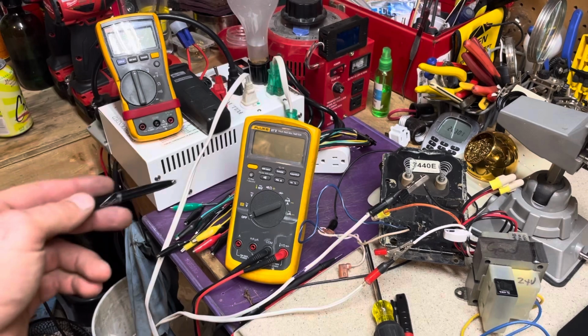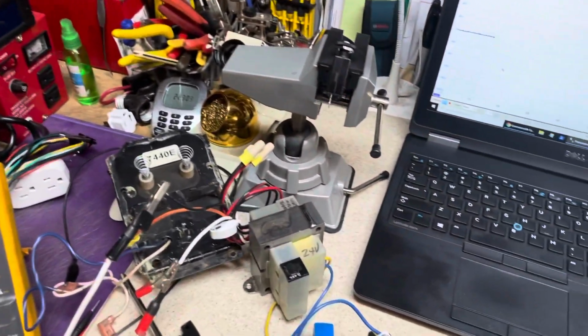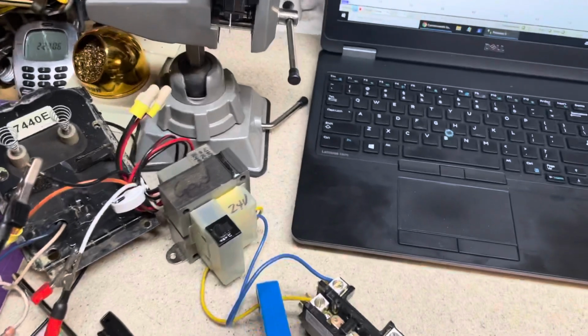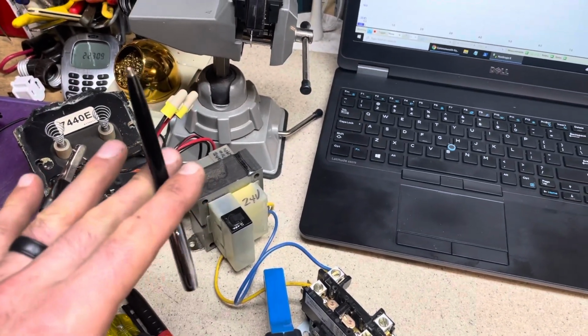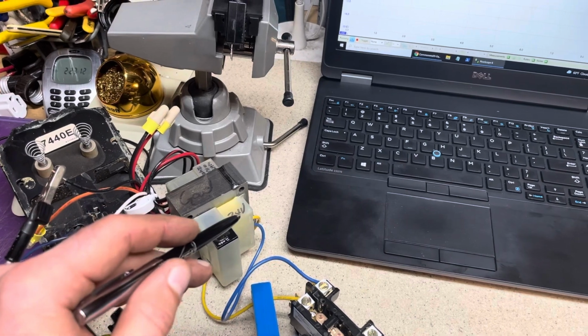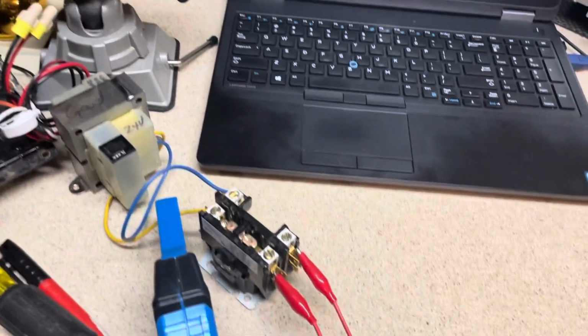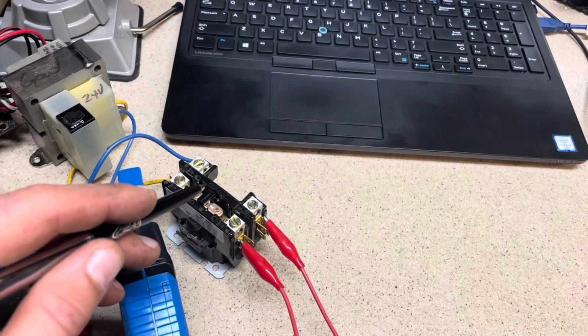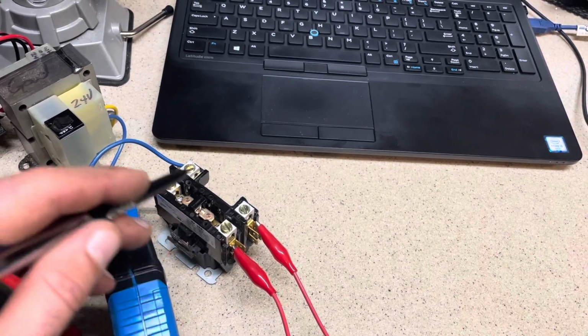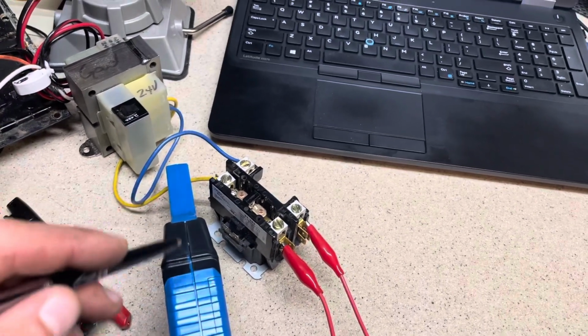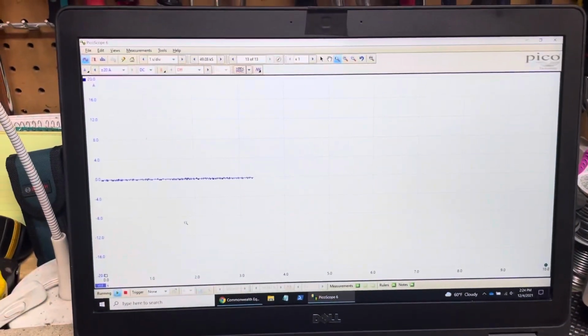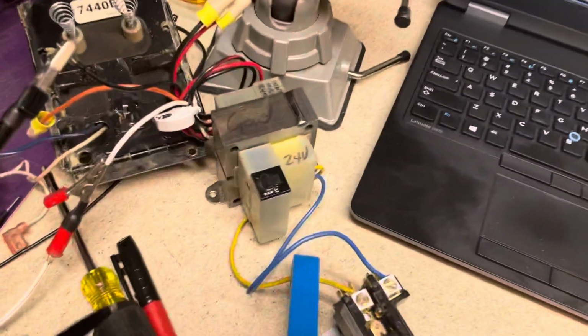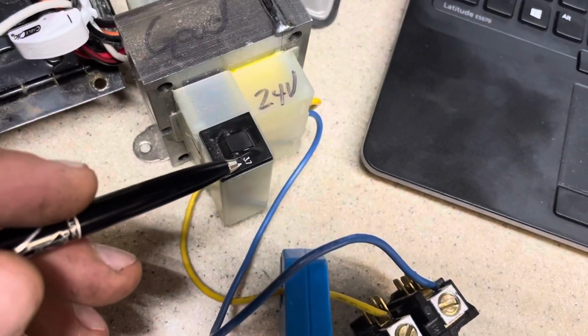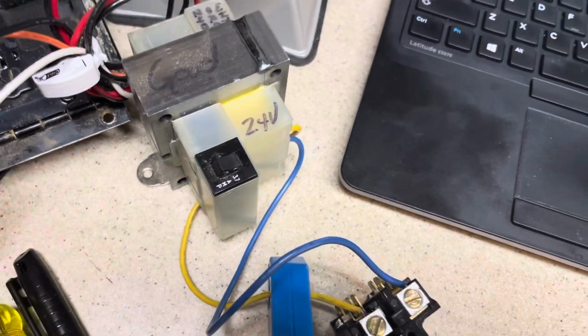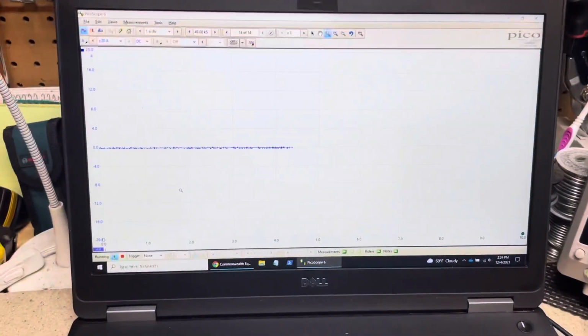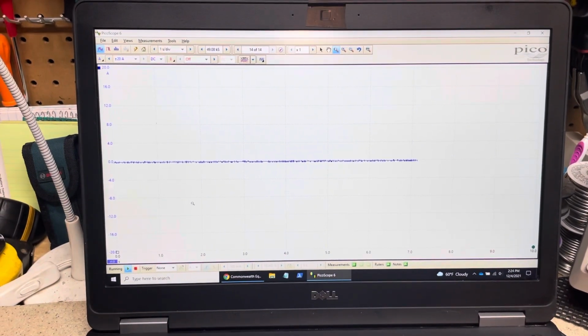I'm connected to my isolation transformer to keep everything safe, or safer I should say. I'm going straight into a normal HVAC transformer, 24 volts AC out the secondary. I'm using a contactor, manually activating it to short the secondary. I have my amp clamp hooked up. Let me point this out: this transformer's protected by a 3.7 amp fuse, and I believe this is a 70 VA transformer. Let's short this transformer and see what happens.